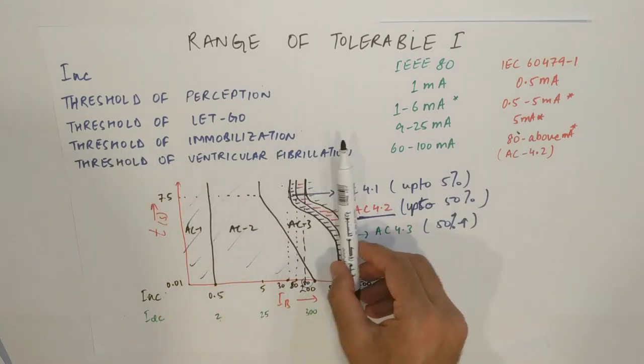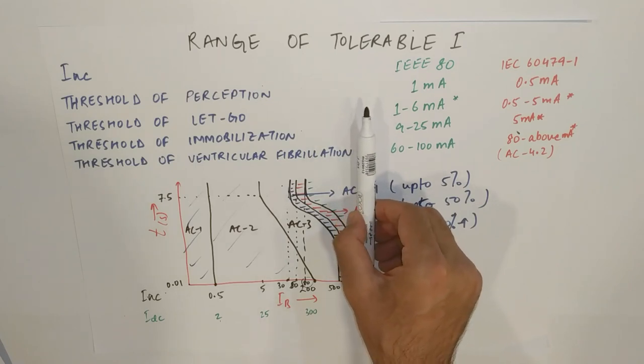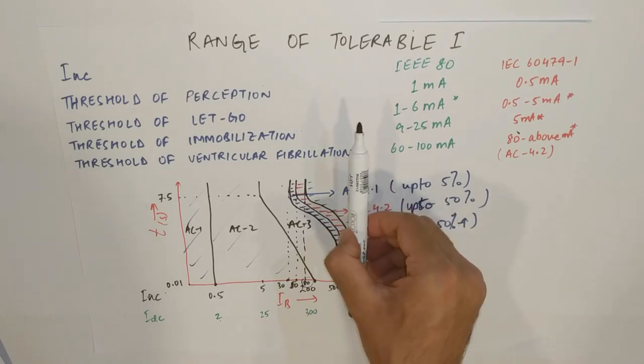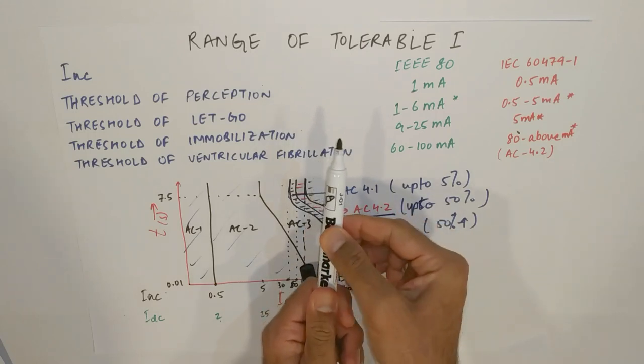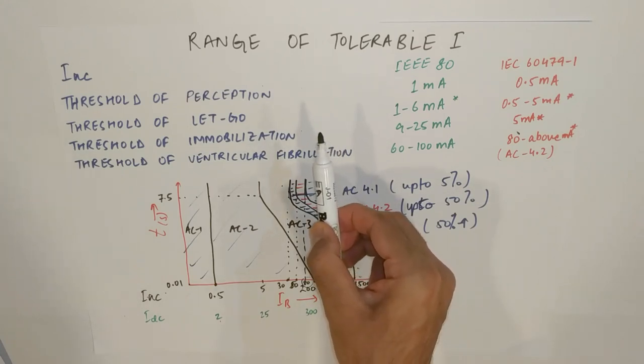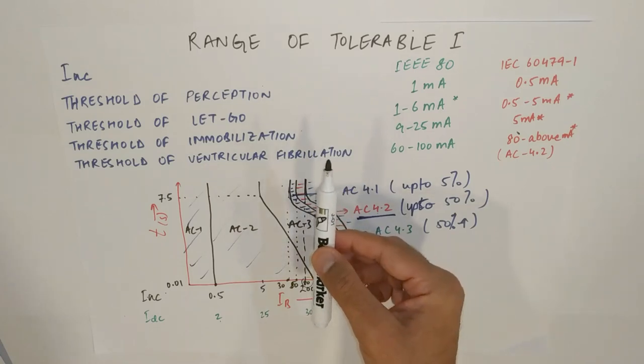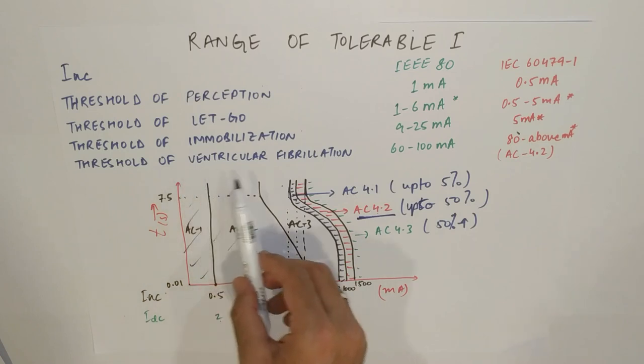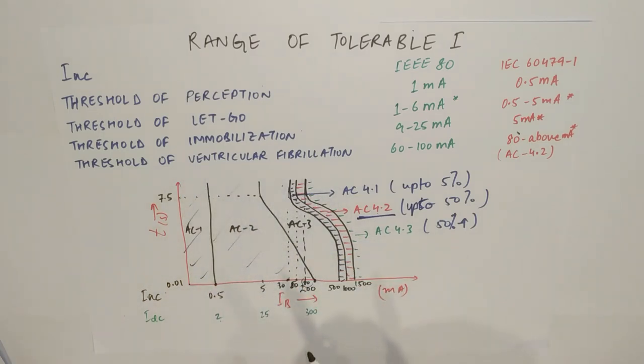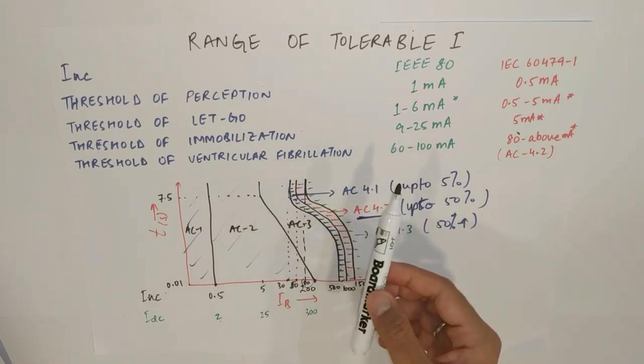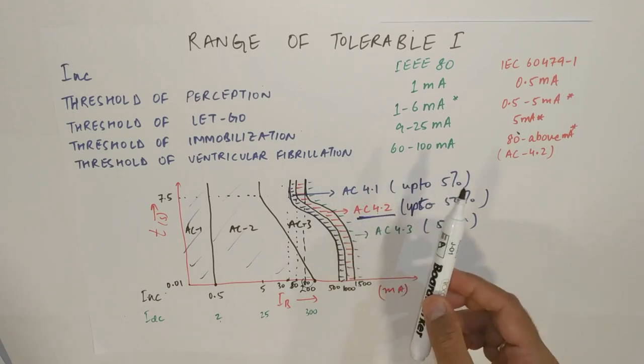Threshold for immobilization. That means if I am touching the frame of the washing machine or this pin and the current is flowing through me also due to a fault, then I am not able to remove my hand. I am trying, but I am not able to remove. I am not able to remove my right hand. So, what will happen? My muscles will contract in this case. And I am unable to remove it till this current stops flowing. That means the circuit breaker gets open. In this case, this value is 9 to 25 milliamps as per IEEE 80. And threshold for ventricular fibrillation. This is the most important. This leads, ventricular fibrillation, then eventually leads to stoppage of heart or inhibition of respiration and causing injury or even death. This is the value which is 60 to 100 milliamps as per IEEE 80.